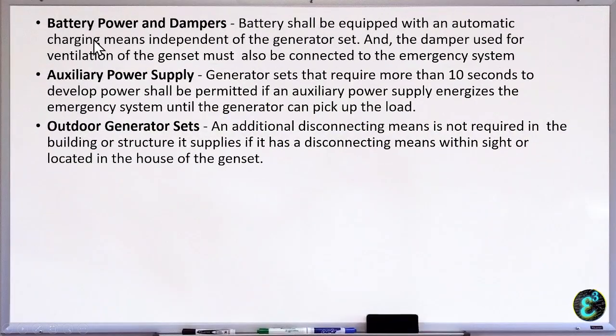Okay, then battery power and dampers. So, battery shall be equipped with an automatic charging means independent of generator set. And the damper used for ventilation of the genset must also be connected to the emergency system. So, the ventilation of our emergency system, or our emergency equipment, shall also be connected to the emergency system.